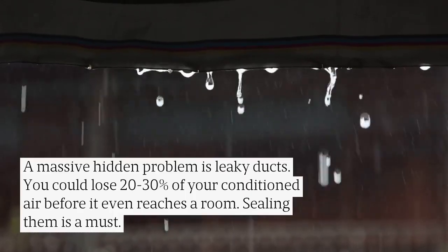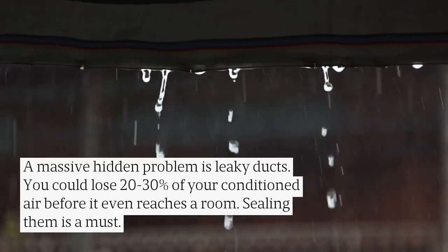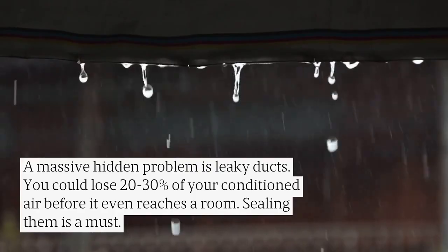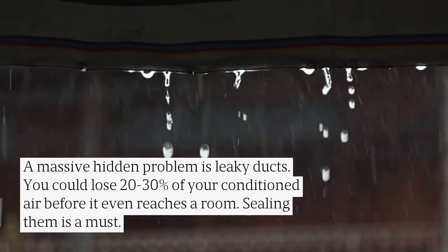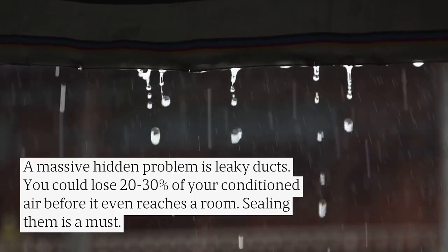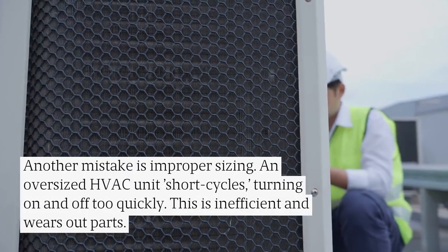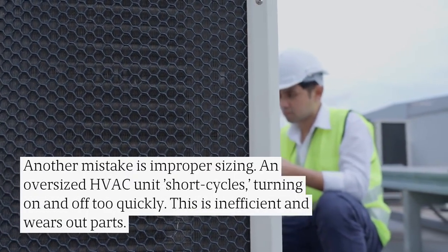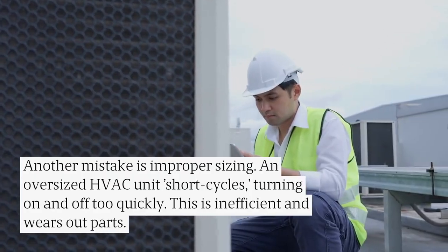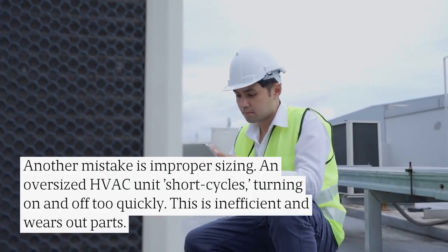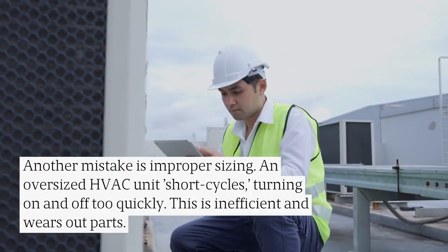A massive hidden problem is leaky ducts. You could lose 20–30% of your conditioned air before it even reaches a room. Sealing them is a must. Another mistake is improper sizing. An oversized HVAC unit short cycles, turning on and off too quickly. This is inefficient and wears out parts.